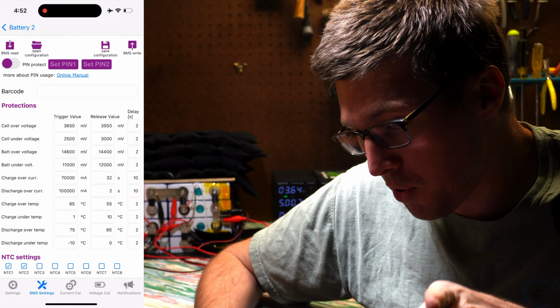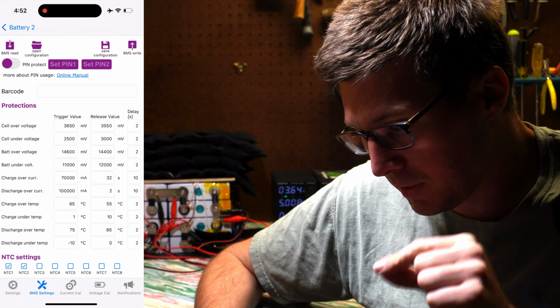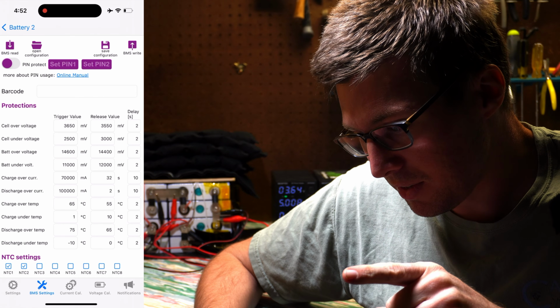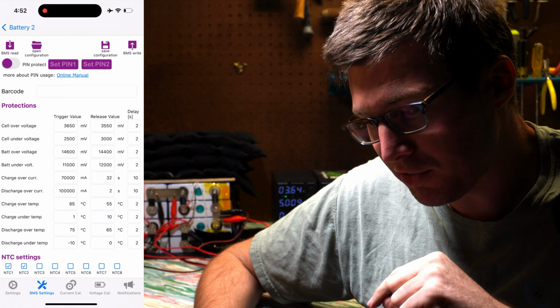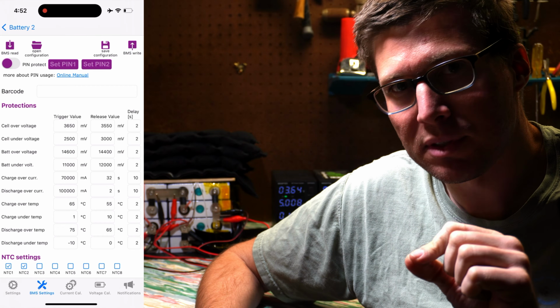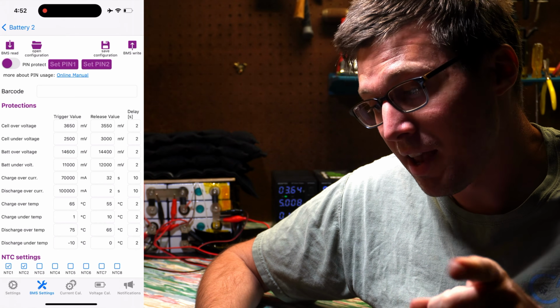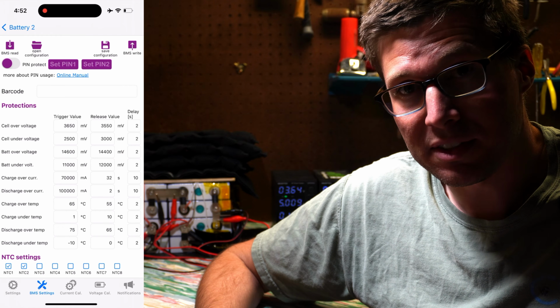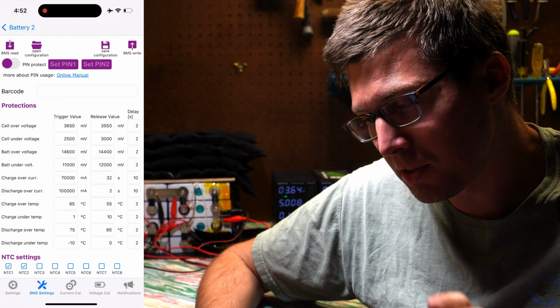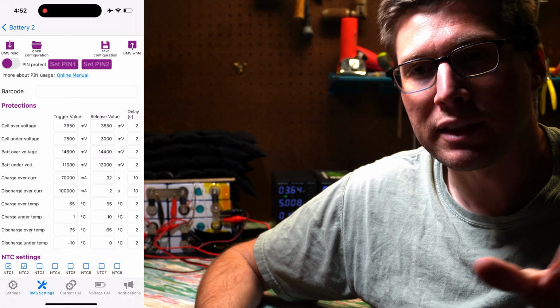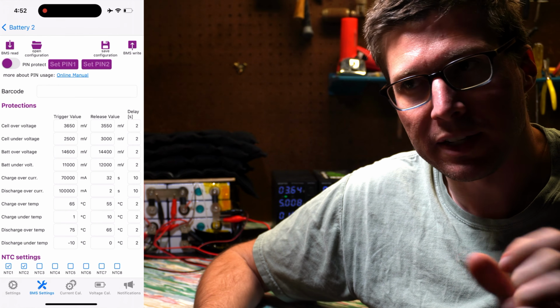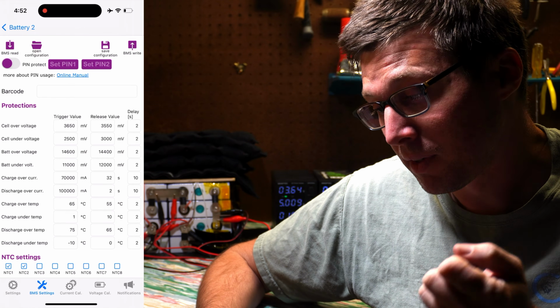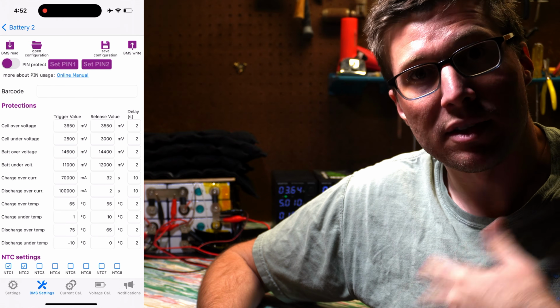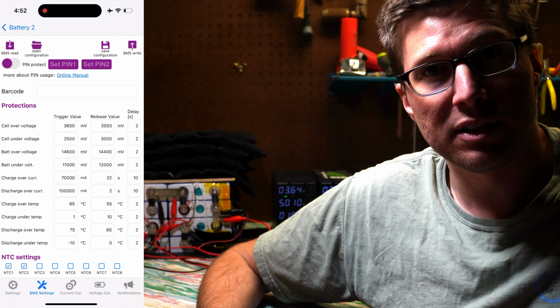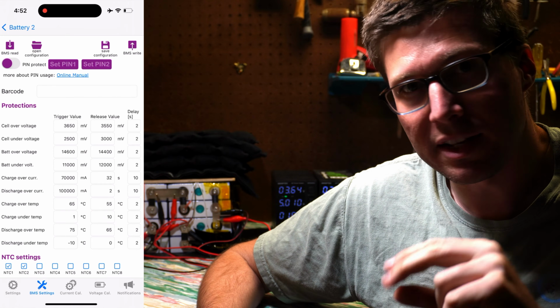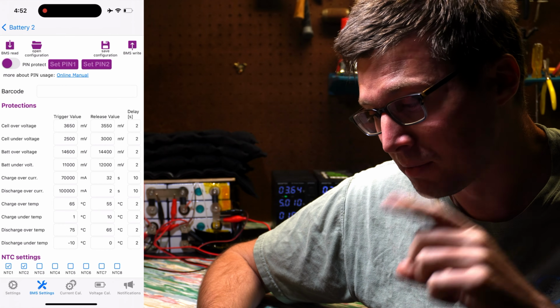With the charge overcurrent, it releases after 32 seconds, 10 seconds after it trips. It has to hit 70 amps for 10 seconds and then it cuts off, waiting 30-32 seconds. That's to give time for whatever's happening, like a solar flare or whatever, to calm down before it starts the batteries again, because restarting is a lot of abuse on the BMS.